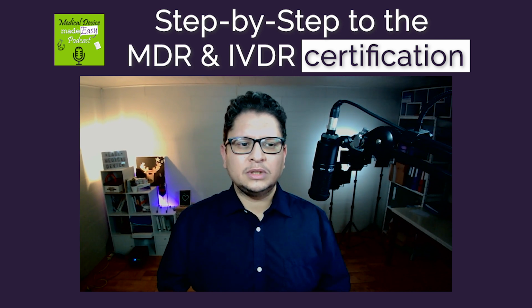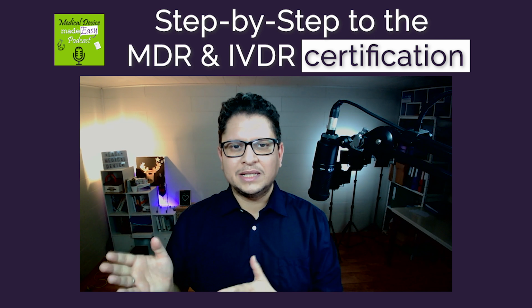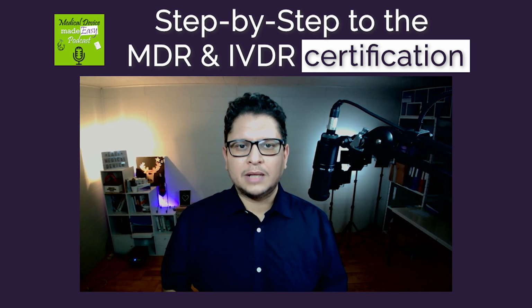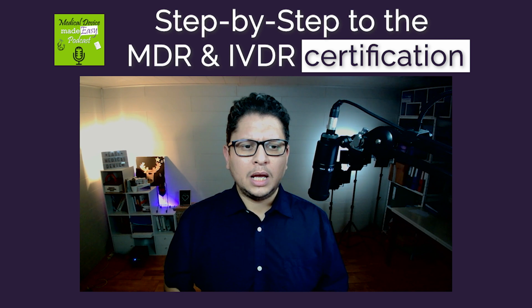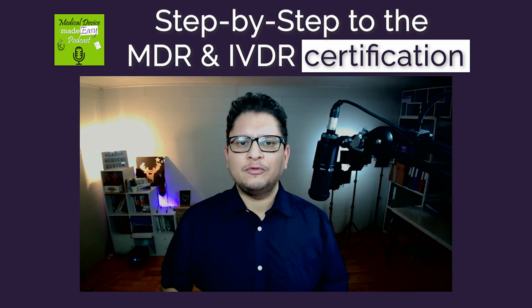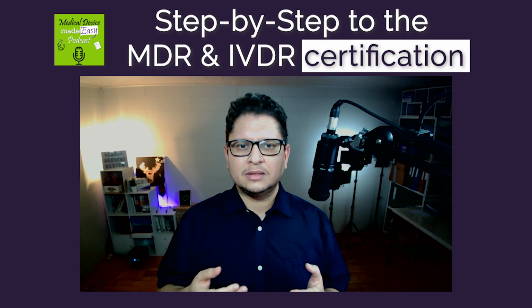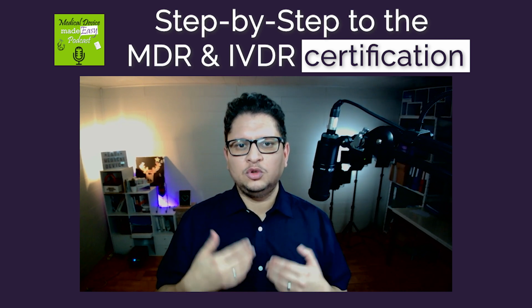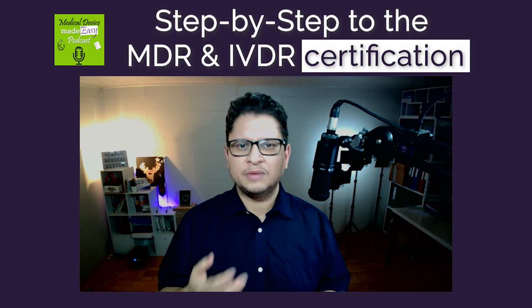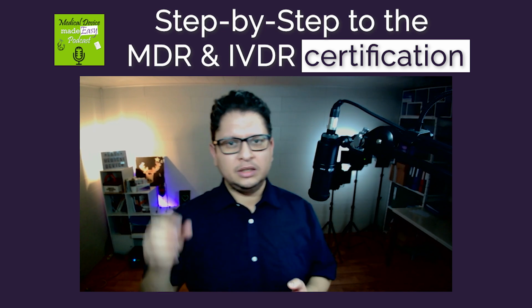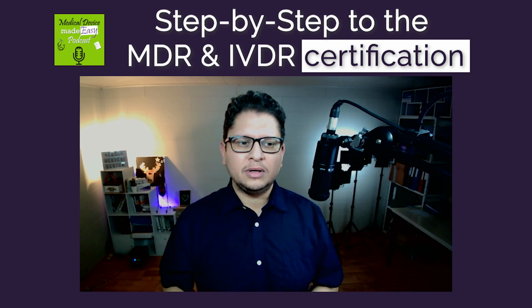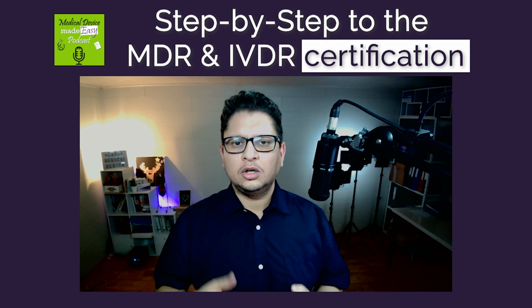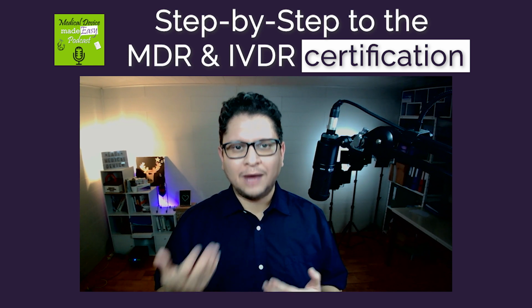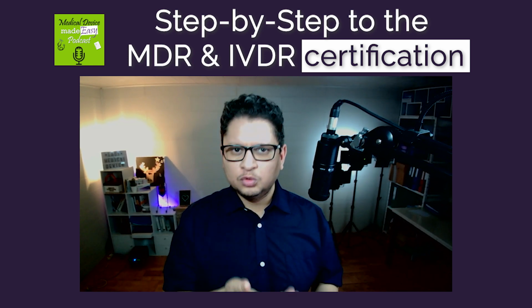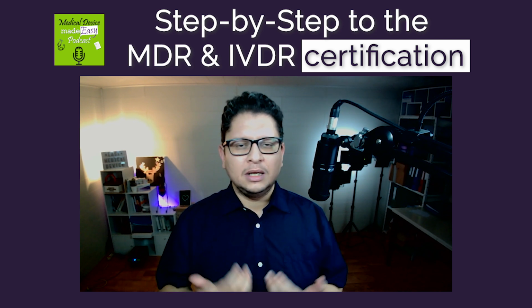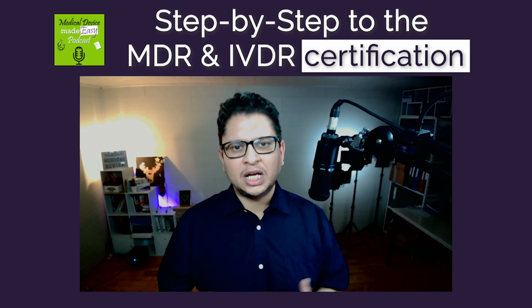So here is what I wanted to say to you in terms of the process to get certified from A to Z. It's, as I've said, a long process, and it's something where you have really to be disciplined, and you have to understand that a notified body is here really to verify that you are following the process. So there is no kind of negotiation here. It's more like I'm checking, is it here? Yes, no, etc. You still have to argue, because you are still the expert of your product. So you have to argue about the fact that no, your product cannot do this or cannot do that because of this argument. So you are still the expert, but the notified body will really challenge you for that.